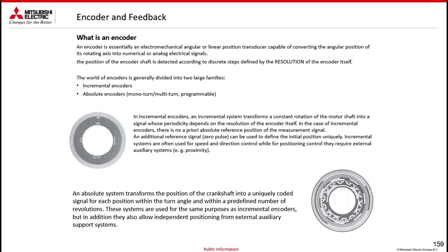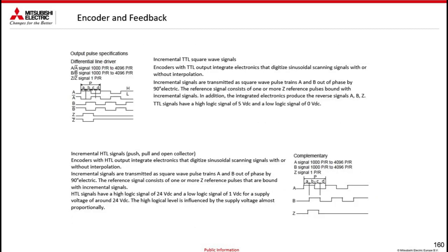Then, well, I have this little parenthesis on the absolute encoder, which has the particularity of having n tracks, where each track has a different binary coding, which gives me the precision of the absolute position in the rotation angle. The encoders readable by the inverter are of two types: line driver or classic open collector, where the signals are TTL rather than HTL. The difference is that usually the line driver is preferred, because it is less subject to disturbances, because it has the phases plus their negations. So A negated, B negated, Z negated, unlike the classic open collector, which is A, B, and Z.